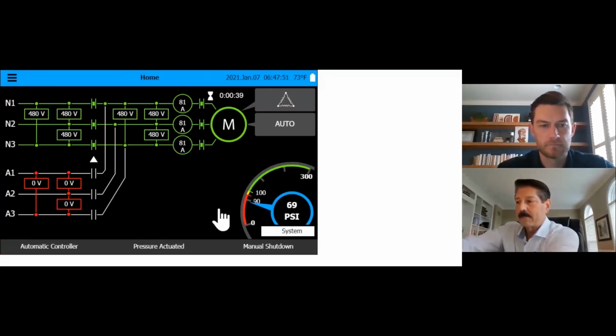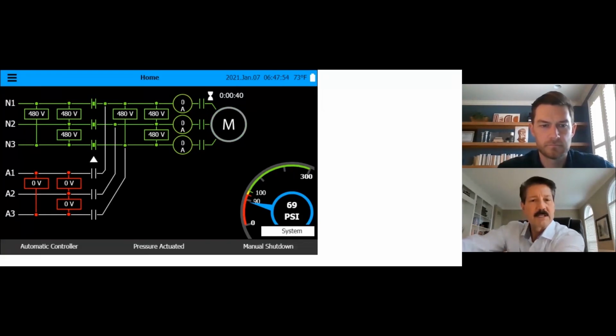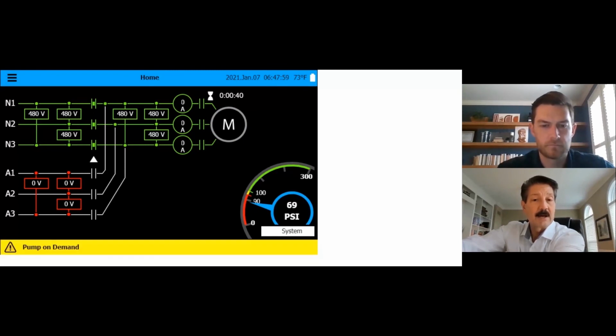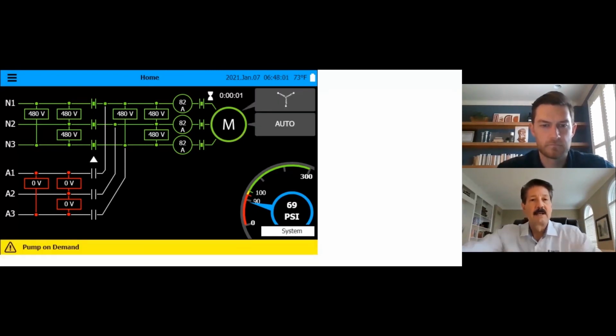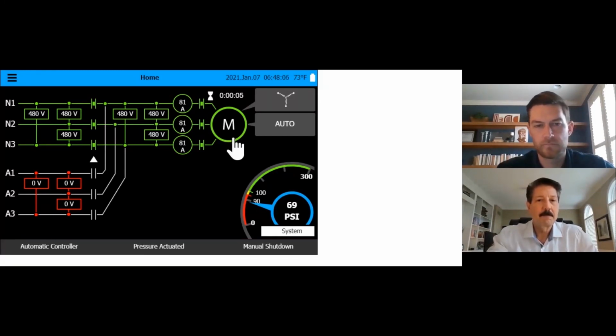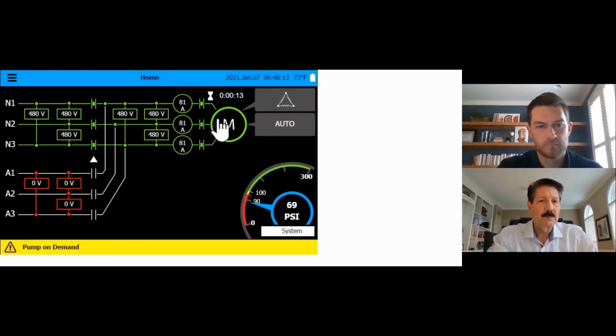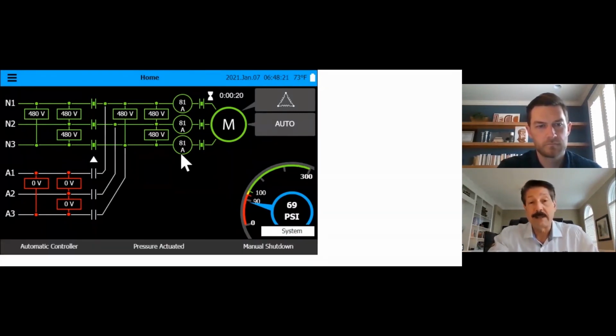So I'm going to stop. I'm going to press the stop button one more time. I want you to see this. The pump on demand is there because we're below 90 PSI cut in. We're at 69. So hence, the signal to start the motor happens. Pump on demand and auto. It tells you why it started. Again, the green ring around the motor designates that it's energized or on. As you see, the contactors are closed. You see the ammeter. We're talking 81 amps across each phase, which is fine. It's normal. You can visually see that.